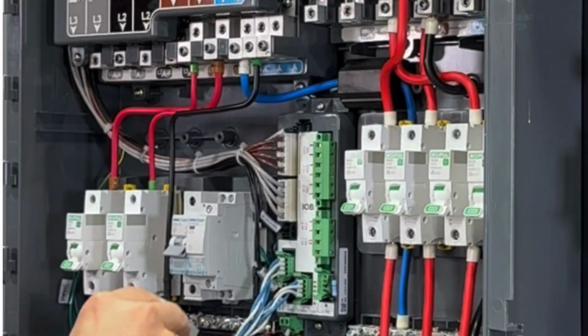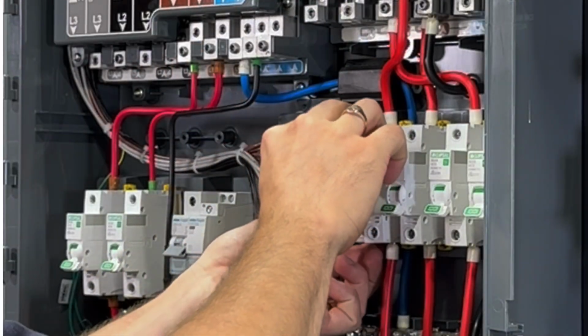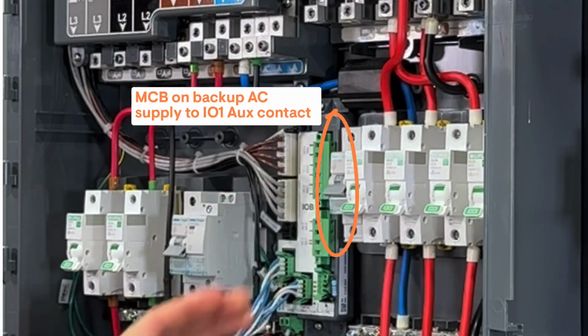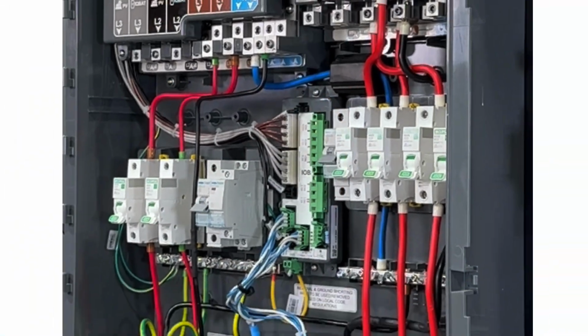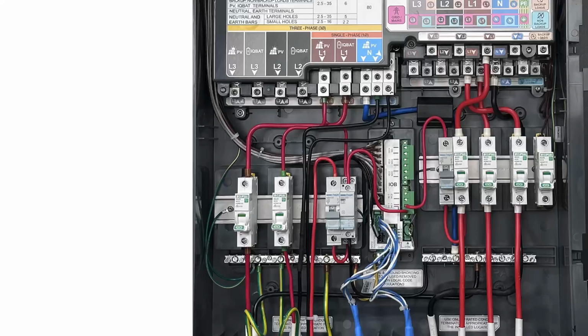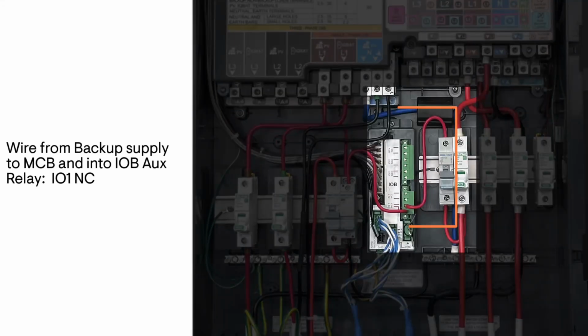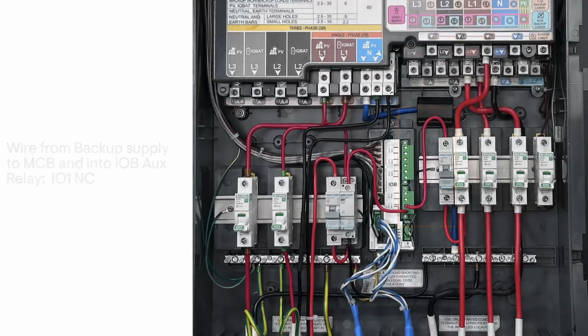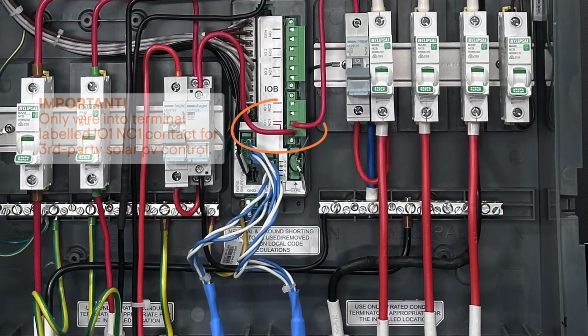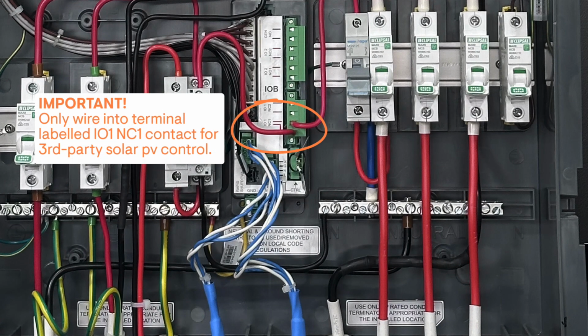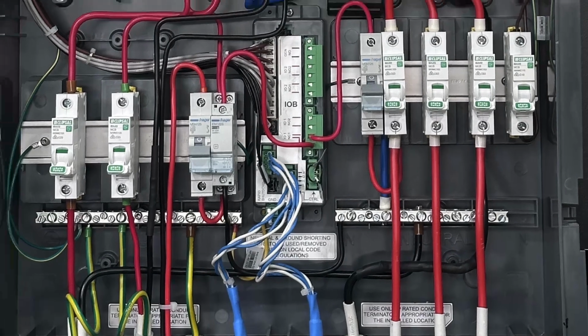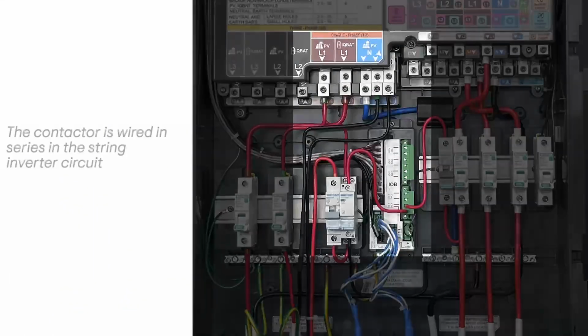Wiring configuration. The MCB is wired from the backup AC output within the IQ system controller and connected across to the I/O auxiliary relay contact identified as IO1 NC1. It is critical that IO1 is used for string inverter control wiring. If another auxiliary contact is selected, the Enphase Installer App will not allow configuration of the contact during commissioning.